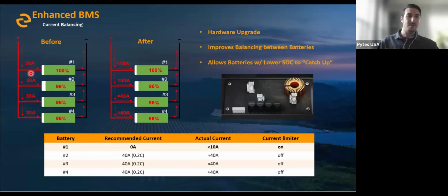Well, as soon as their SOC goes above a certain amount, the BMS will start to limit charge current, right? And it slowly charges the batteries up to 100. But if you have one battery that hits 100% first, but the others have not, that one battery is still going to send an "I'm full" signal to your inverter and tell the inverter to stop charging, right? So you have that battery hitting 100%, whereas the others aren't yet.